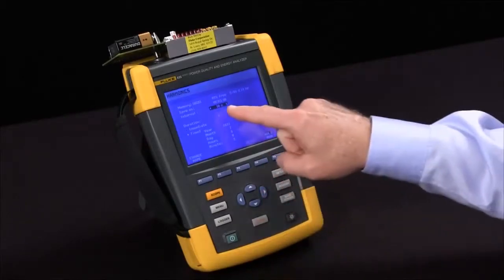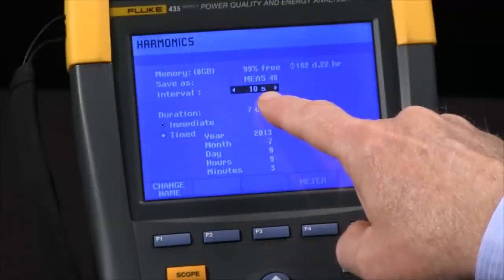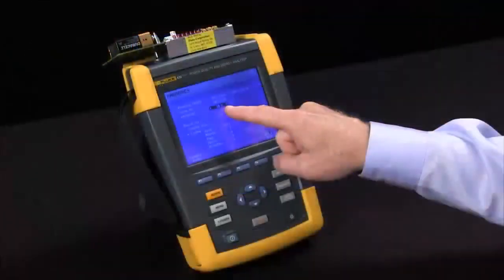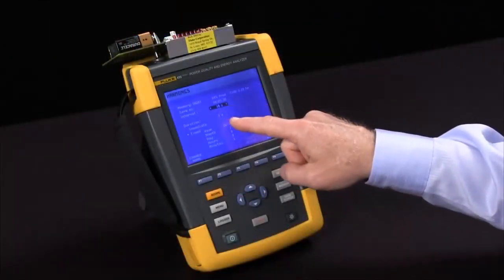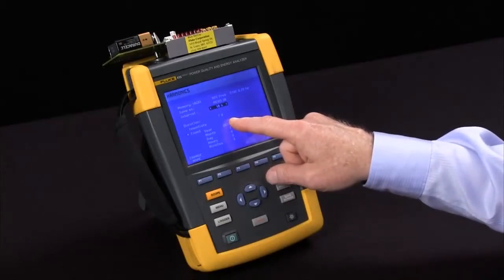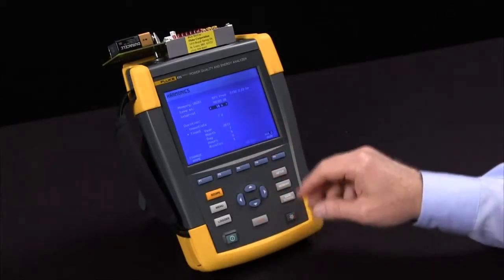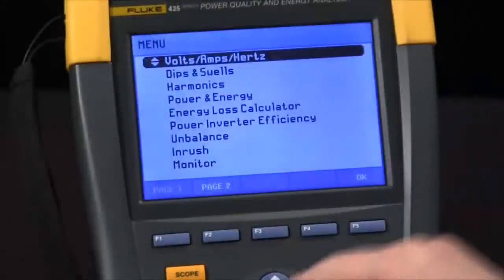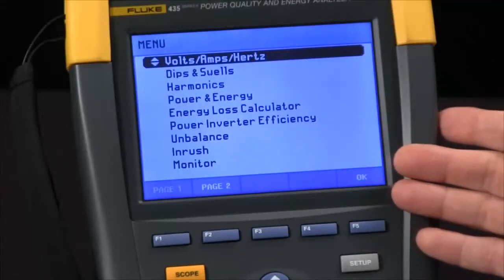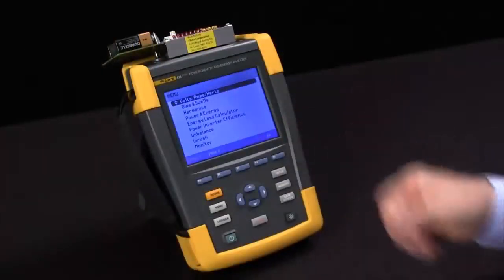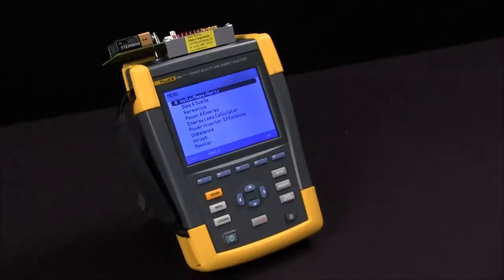We encourage you to keep your intervals at 10 seconds if possible. If you need time resolution down to the second to know when things happen, you can do so for a short period of time, but keep in mind you'll create a large file size. Also, in all of our tests, we'll always have event capture active to capture things happening in very brief periods of time. And that's how we configure the Fluke 435 for trend configuration.